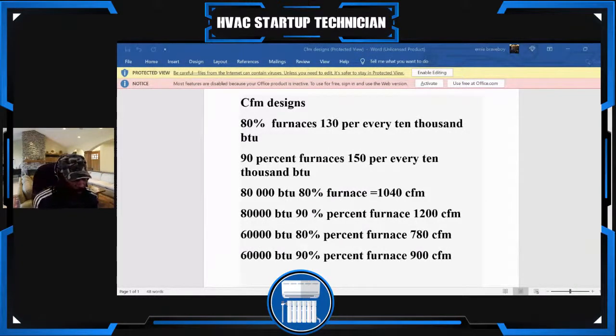You can see we're talking about CFMs and designs, and these are important numbers that you should know. On my screen I have an 80% furnace. We need 130 CFM for every 10,000 BTU. There is a really easy way to work that math out. If you're working on an 80,000 BTU furnace, we do 130 times 8, and that will give you approximately 1040. But that is not where you end.